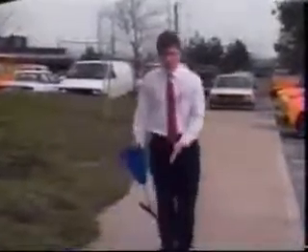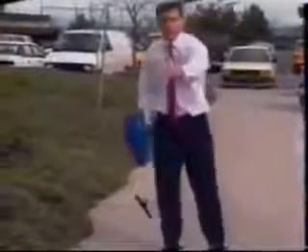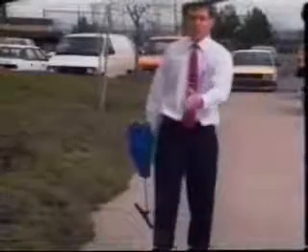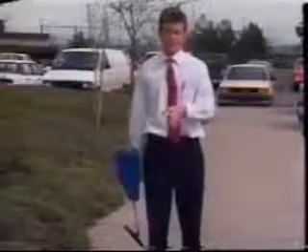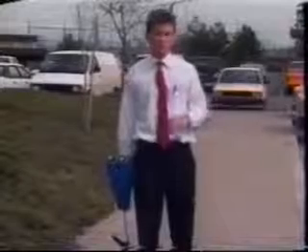So if we go down this run, and let's say I get a long side and a short side on my depth readings, and that continues along this run, you could almost be assured that you have another utility down there. So it does give you useful information about your utility, although you cannot get depth. And remember, USA, the Underground Service Alert, does not require you by law to give depth to a contractor, so you never have to give depth to a contractor. It would just be for the own internal use of your SMUD district or agency.